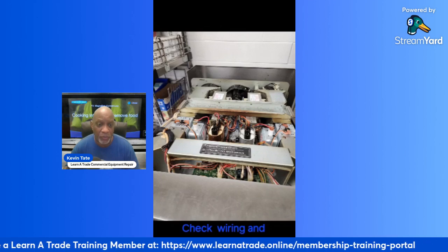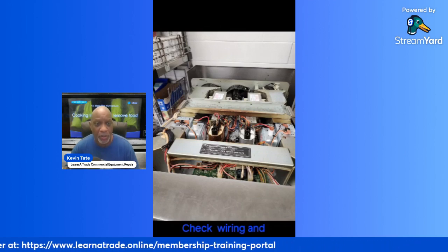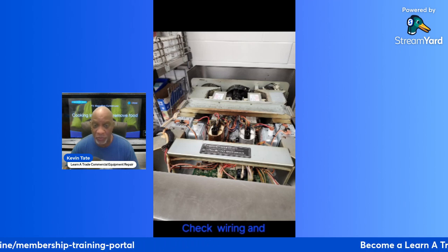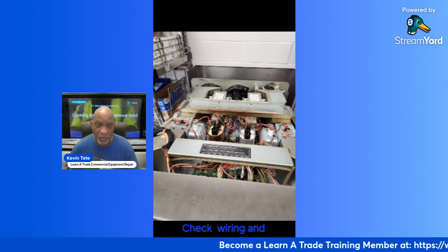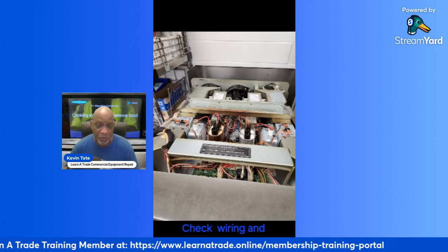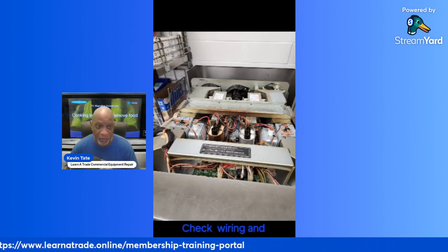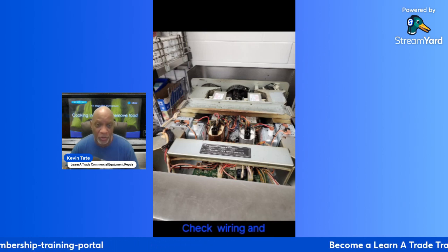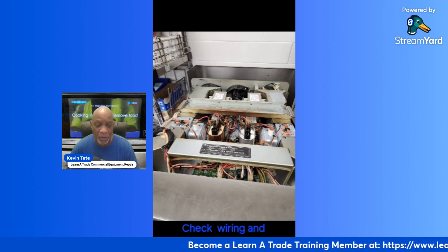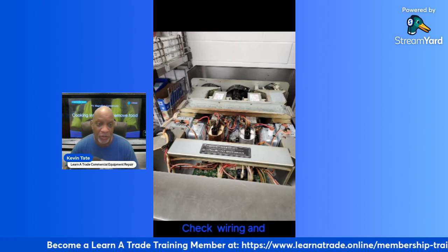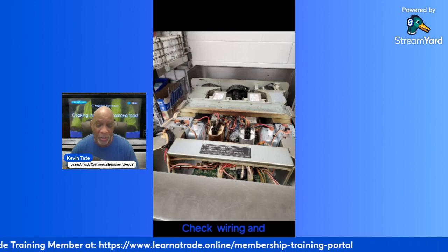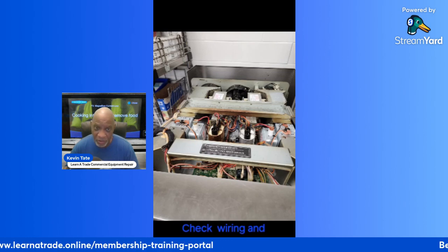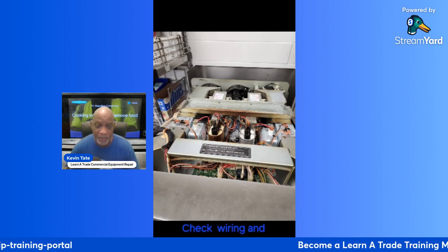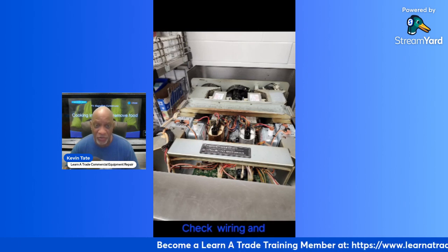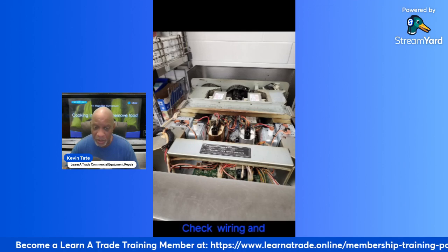And then this is just showing you the top view. Once you got everything installed and in place, you want to go ahead and just do a double check on the wiring that you were testing and stuff like that. Check your high volt transformer wires. Make sure your filament transformer wires are secured, that there's nothing loose. Check your diode wires. Make sure those are all on the terminals that they're supposed to be on. Check your two magnetron wires on each side, and you want to make sure that that red wire is going to the FA terminal. And then you want to check your capacitor wires just to make sure that your wires on the capacitor are secured.